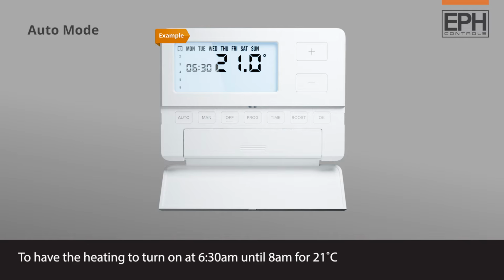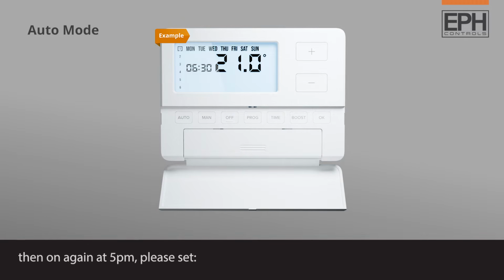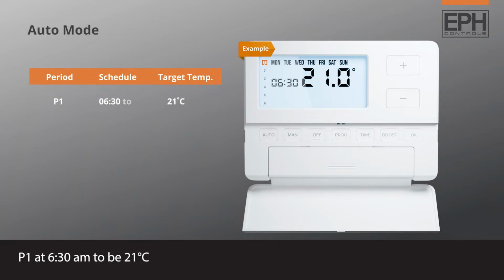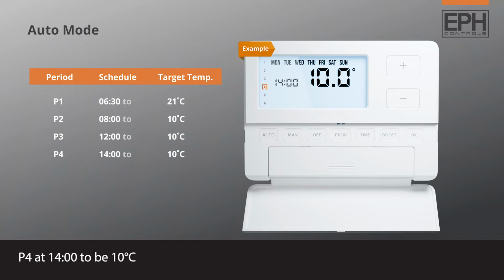Example, to have the heating turn on at 6:30 am until 8 am for 21 degrees, then on again at 5 pm, please set P1 at 6:30 am to be 21 degrees, P2 at 8 am to be 10 degrees, P3 at 12 o'clock to be 10 degrees, P4 at 1400 hours to be 10 degrees, P5 at 1700 hours to be 21 degrees, P6 at 2100 hours to be 10 degrees.